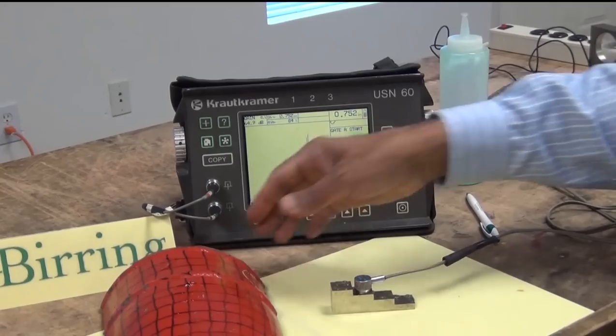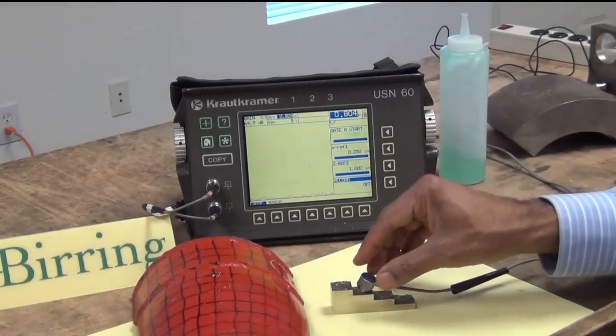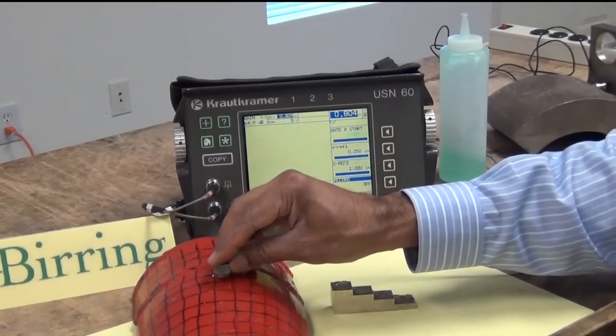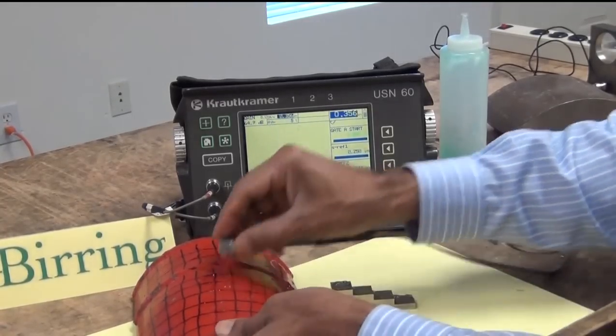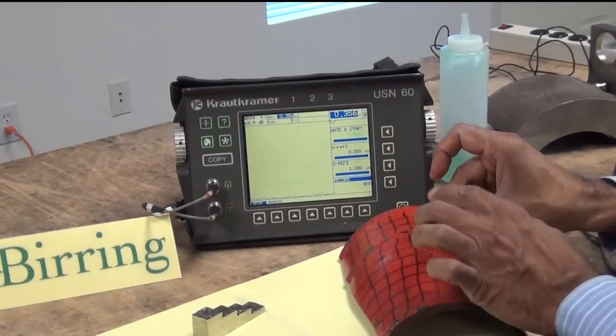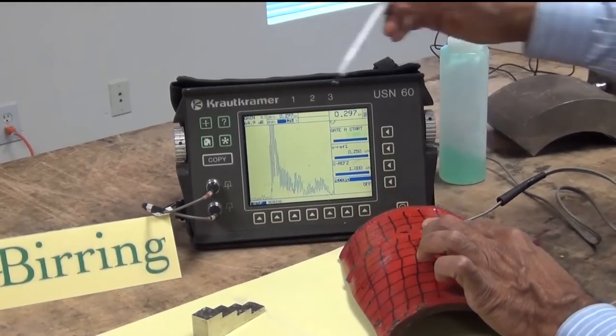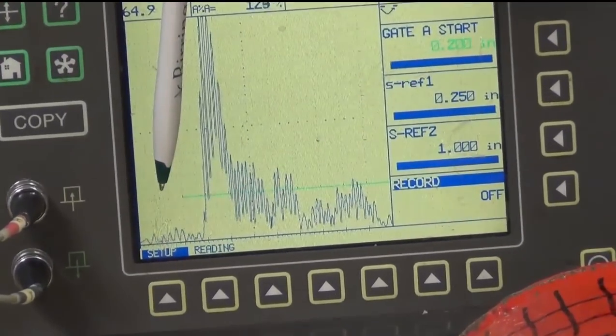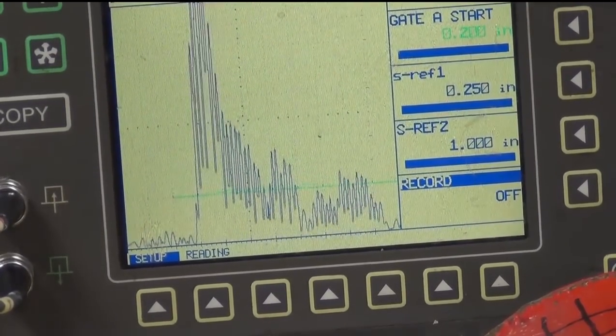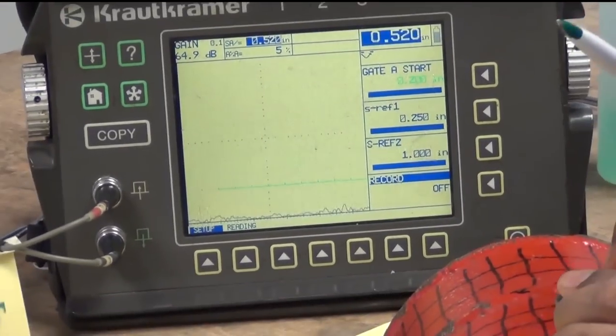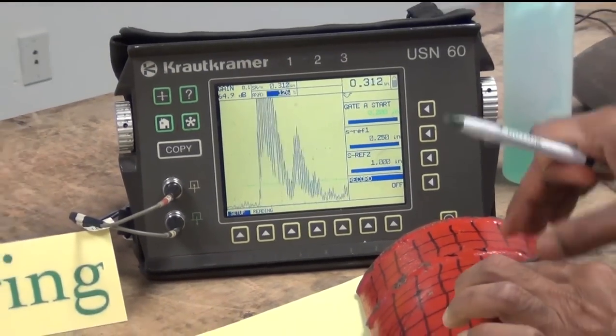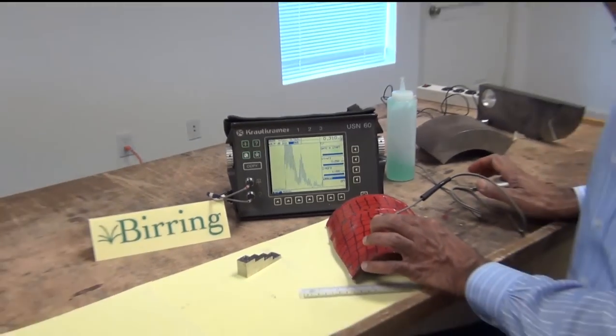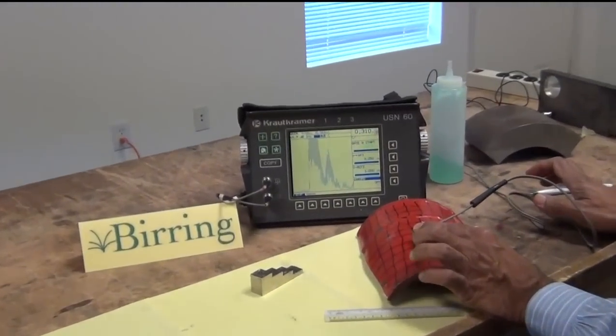Now we are ready to take the thickness measurement on this cutout. I will place the probe on the sample with some couplant on it. And as you can see the screen, it's reading. This is a 1 inch screen which means this is 0 and this is 1 inch. So it's about 0.1, 0.2, 0.3 and it's reading 297. If I go here it's reading 310. So that is a quick demonstration of the thickness measurement set up with a dual probe.